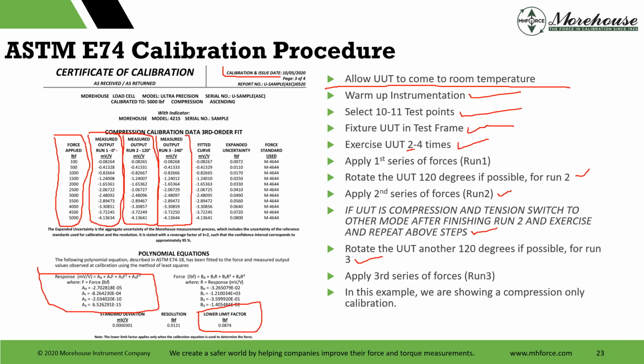Then we go run the data. At this point, we're looking for irregularities, and we're also comparing against previous data if we've had it. So we do a lot of cross checks, and we've been more vigilant at trying to look at the lower limit factor. This one says 0.08. If the last time it was 0.1, we're like, yeah, we're good to go. We're lower than last time. If the last time it was 0.05, we're going to start doing checks. We're going to start looking at the data in more detail and make sure we didn't have a weird point or something else going on.